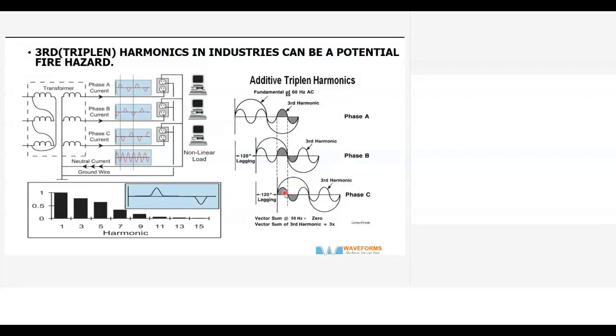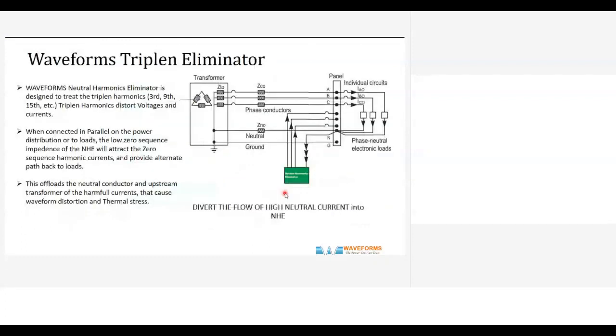Normally you have 4-wire cables only, sometimes 3.5. So you'll have to double the neutral and so on. In spite of that, you cannot eliminate the neutral heating without eliminating this third harmonic. So this third harmonic is a serious problem in many installations, especially single phase ones like residential areas or data centers.